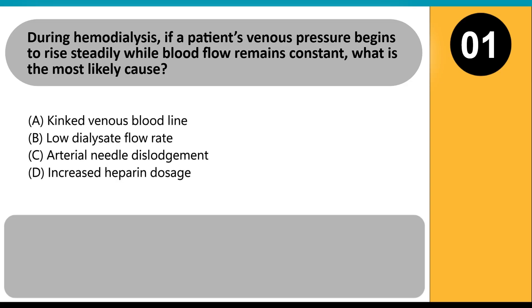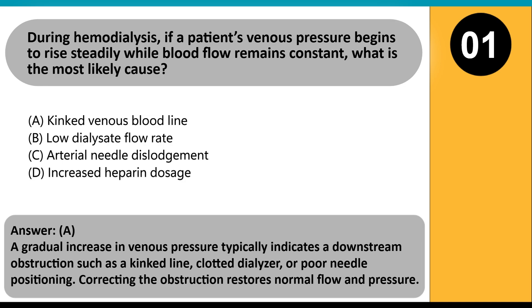During hemodialysis, if a patient's venous pressure begins to rise steadily while blood flow remains constant, what is the most likely cause? A. Kinked venous bloodline. B. Low dialysate flow rate. C. Arterial needle dislodgement. D. Increased heparin dosage. Answer A. A gradual increase in venous pressure typically indicates a downstream obstruction such as a kinked line, clotted dialyzer, or poor needle positioning.